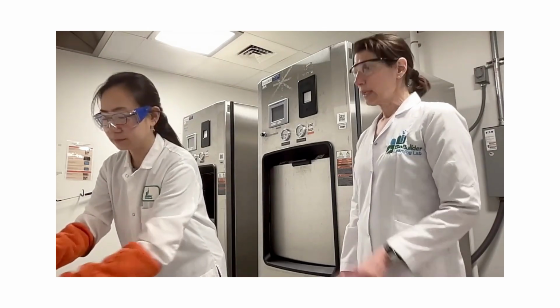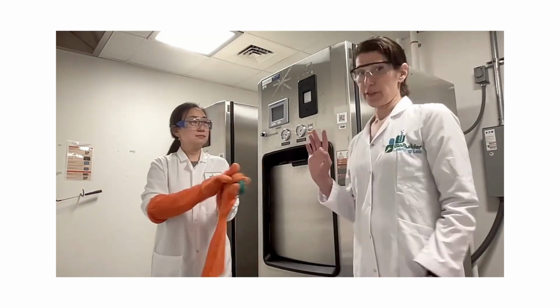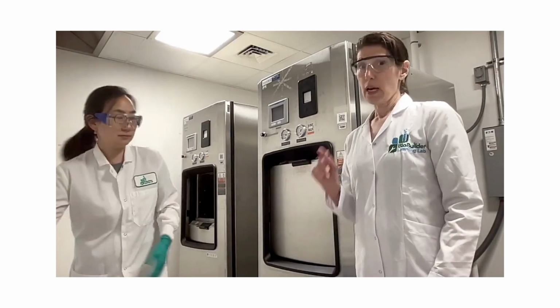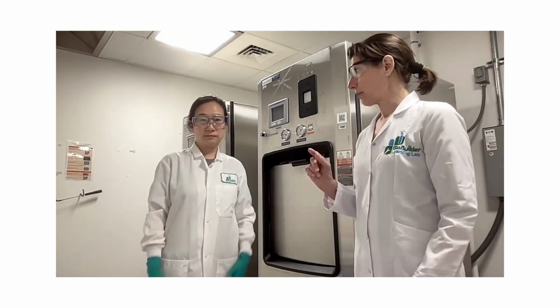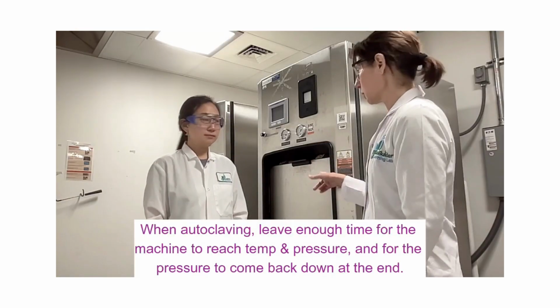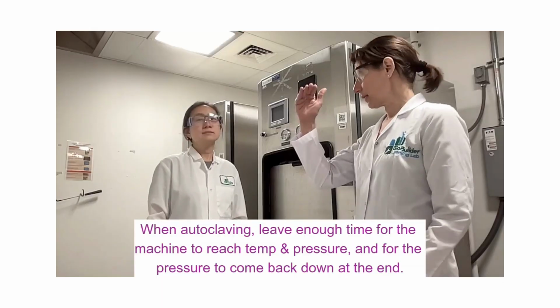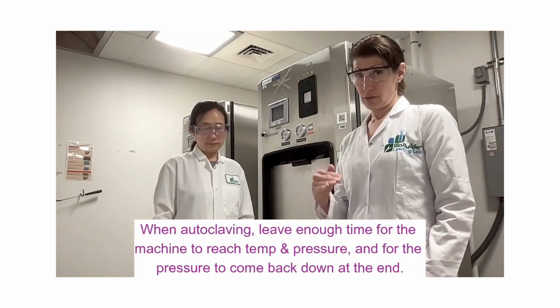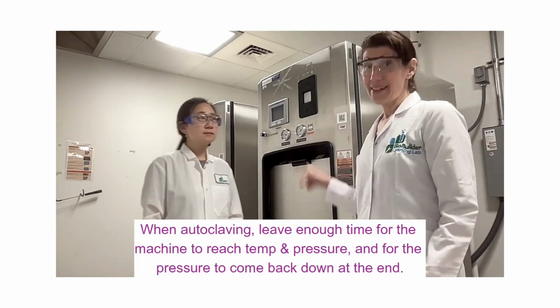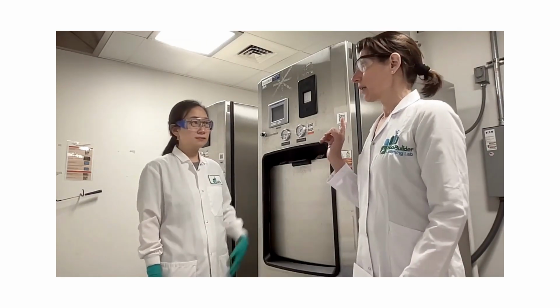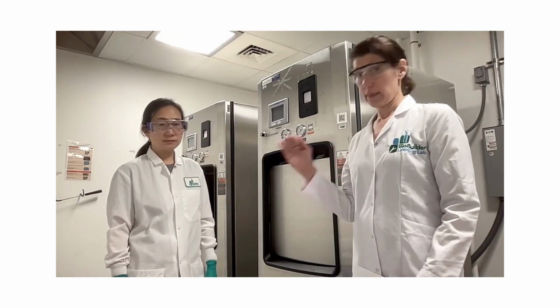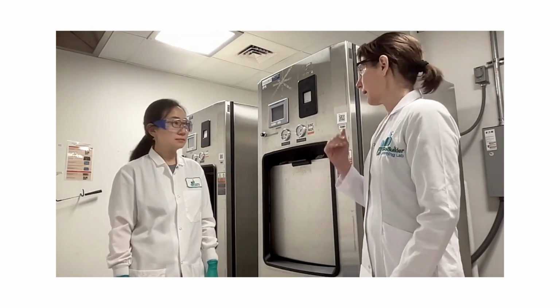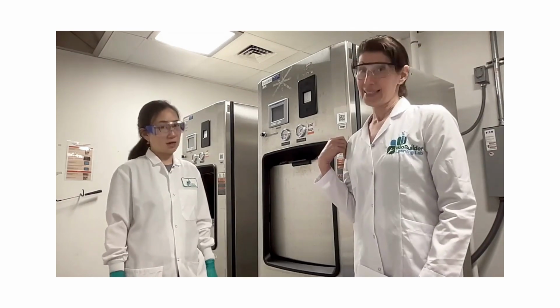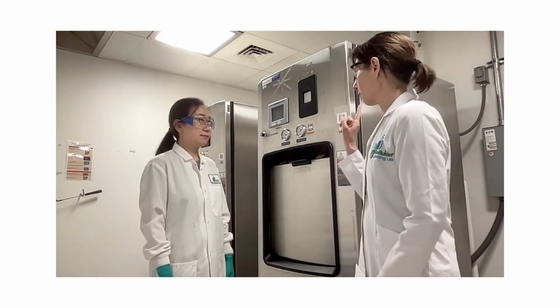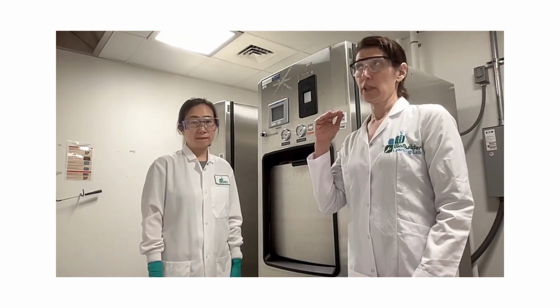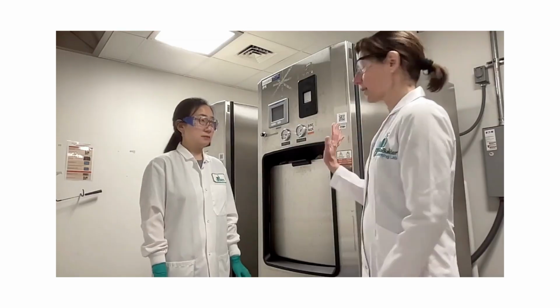One tip is that we've said that we want to autoclave for 15, 20, 25 minutes. Do not plan for just that amount of time if you're trying to run an experiment and have something sterile, because it takes some time to reach that temperature and pressure, and it takes time to come back down. You cannot open the door until the pressure is back to atmospheric, so 1 psi, and that can take some time to vent. So even though we are autoclaving at that temperature for a given amount of time, the whole process will take longer than that.